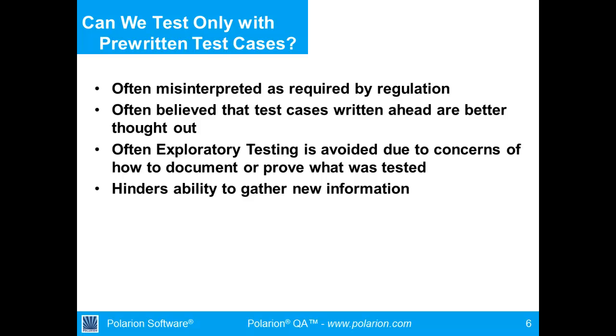That ties into the way I usually do it, where I have fairly tight scripts around the high-risk feature functionality or pieces of products if there's safety issues potentially, where I want the person who is aware of the dangers or the criticality of the functionality to a patient to put thought into a script and make sure that the person who executes that particular script is actually executing it. But for things that are not quite of that degree of criticality, I really like using screen recordings and miking up my testers, and I will record the entire test session during that point in time. Movies and recordings of what people actually do is a lot stronger evidence of what actually happened as opposed to a printed sheet with a stack of screenshots with a pre-recorded script of what they allegedly did. So that tends to be my approach.